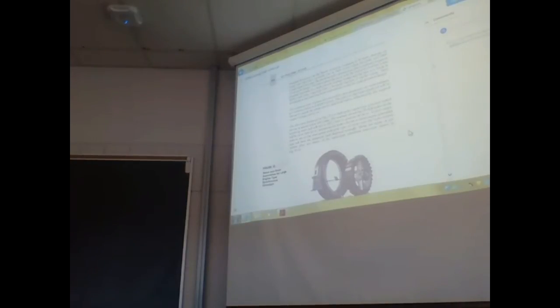The alternator, illustrated here in Figure 12, is a multi-pole engine type generator typical for use at speeds below 500 RPM. The machine shown has 28 field poles on the revolving rotor and runs at 257 RPM to generate 60 Hz. Typical output will be up to 5,000 kVA.